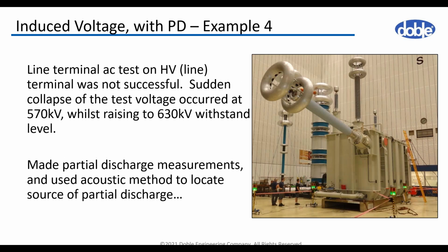And one more example from our practice in the field: we have a single phase HVDC transformer, which during the IVPD test indicated a problem at 570 kV, but the test voltage was 630. We were not able to reach that level because we exhibited a collapse of the voltage at 570 kV, and then the manufacturer decided to stop the test because of this failure.